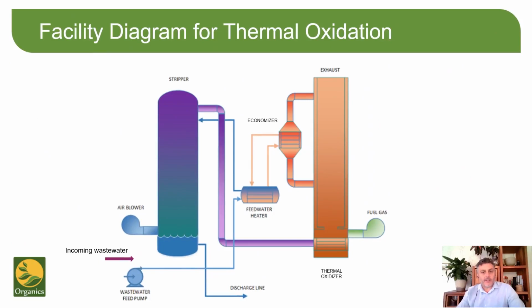This is a component layout to give you an idea of the flow of the system. This particular layout removes and destroys the ammonia and is the typical configuration we have used historically. On the right-hand side, there is a thermal oxidizer that receives fuel gas, typically landfill gas, and burns it to generate heat. Using high-temperature fans, the exhaust gas generated is drawn out of the thermal oxidizer and through a waste heat recovery unit. Here, the heat is taken from the gas and put into a high-pressure hot water circuit running at around 10 bar and 140 degrees centigrade. This high-pressure hot water is then pumped to where it is needed in the system to heat the wastewater and the stripping air as required.